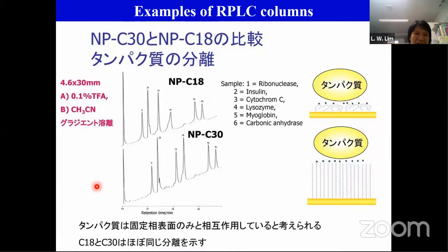This one is because of the pressure. Pressure of the column. So when your system pressure changes, you have drift. We call it a drift. The drift will go up, sometimes the drift will go down.